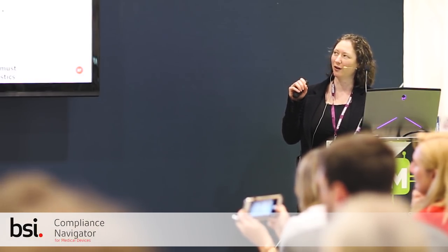So, as part of clinical evidence, we get into lots of discussions about equivalence and what is equivalence and what's the change between what we're doing now and what's required in the MDR. And this slide just gives you a bit more detail about MedDev 2.7.1 and the difference between revision 3, revision 4, and what's required in the MDR. I think there was a big change between revision 3 and revision 4 in terms of the detail in the guidance. I don't think there was inherently anything different in terms of what you should have been doing. It's just that revision 4 told you in more detail about what you should have been doing.